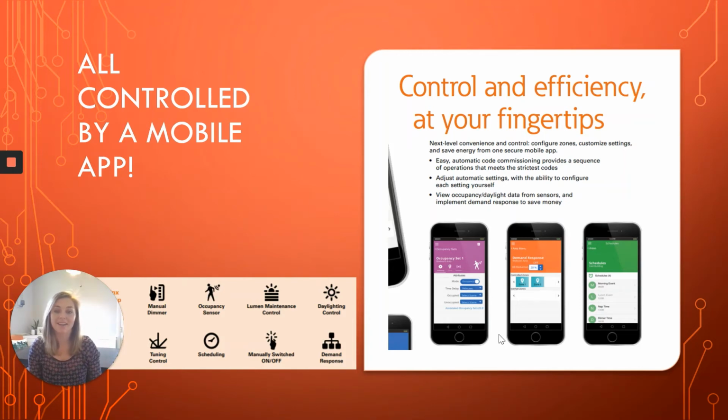Your phone is not going to be needed in every room. There will not be an iPhone or an iPad on the wall for each different space to turn a light on or off. The phone, or the app, I should say, is really just to adjust settings. So to get everything working in order for codes, the way your occupant wants the fixtures to function, or to change something. So for example, if you are designing a classroom and originally you thought the teaching wall would be over here. You want the first row of lights to be really bright for lectures and then the following rows to be less bright. Turns out the teaching wall is on the other side of the room. So there's no rewiring needed. You don't need to adjust each fixture. You literally just drag and drop your fixtures in your app. Super simple.